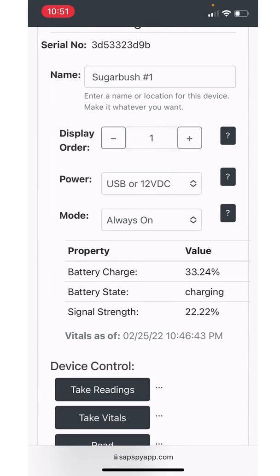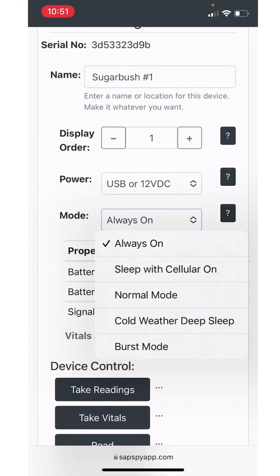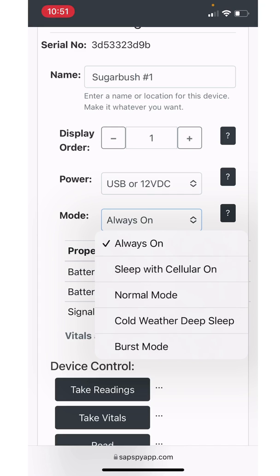All right, in this next area we want to talk about is the mode of operation. There are several modes of operation, whether it's always on, sleep with cellular on, normal mode, cold weather deep sleep, or even burst mode. These all give you a different frequency of readings, allows you to conserve or budget the battery. That is if you don't have constant power on the device. If you have power where your sensor hub is located, you might as well just leave it in either always on, or if you need, you can go to burst mode. The majority of these other settings allows you to budget your battery based on how frequently you want readings. We'll now talk about these in detail.